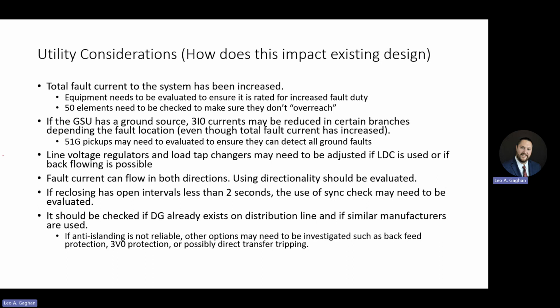5 amps at 80 degrees. Right, they're based on phasors, and they're based on symmetrical components. As these inverters become more and more popular, I'll be interested to see if relays have options to maybe not operate off of sequence components and phasors, but really operate off of a time domain based signal, and what type of characteristics it can derive from those types of signals.